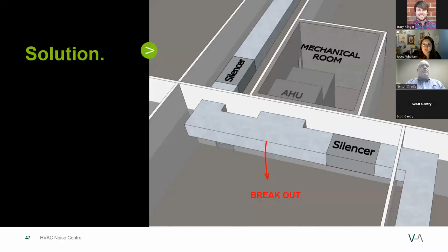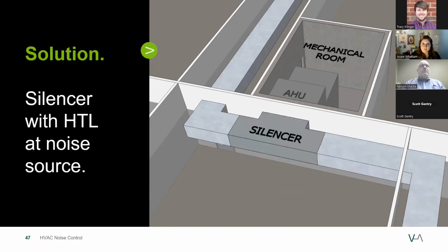So going back to our sketch, the solution is to treat as close to the source as possible. The best location for the silencer would be straddling the mechanical room wall, but this usually isn't practical. The next best location is just inside the mechanical room wall. In this case, there's no space for that. So the silencer would be located right outside the mechanical room. This usually means a high transmission loss casing would be needed to prevent breakout at the silencer. The T shape with the HTL casing would take care of both airborne and breakout noise paths and ensure that the installed pressure drop of the silencer is within ASHRAE guidelines.